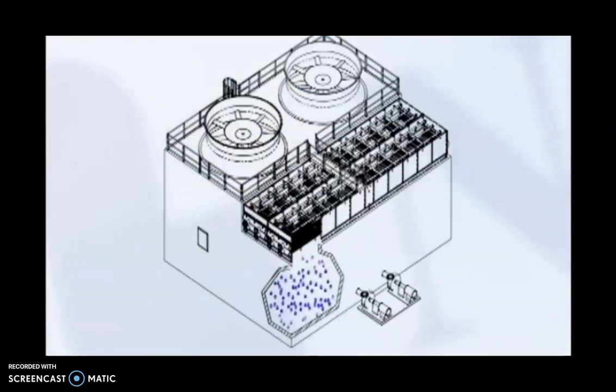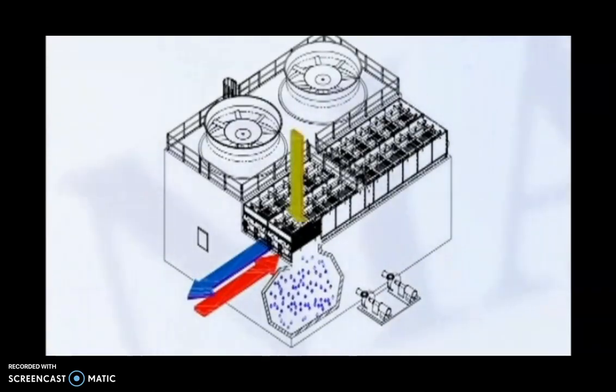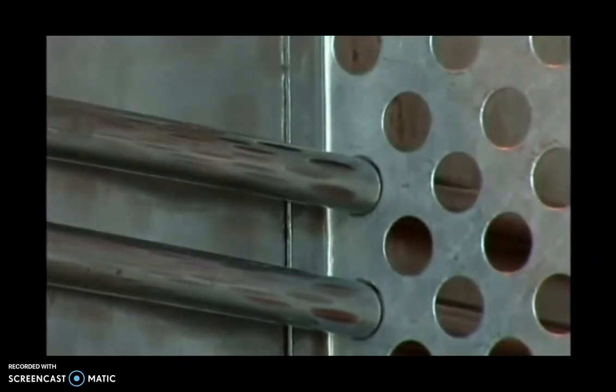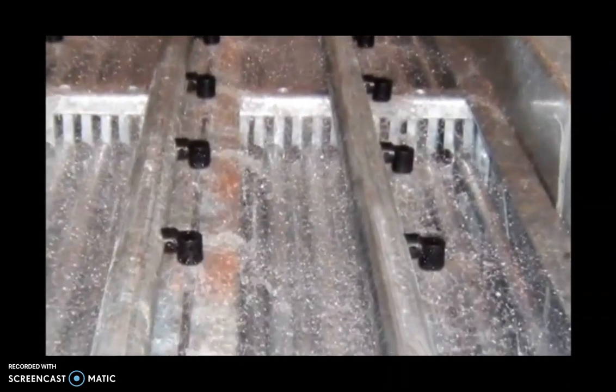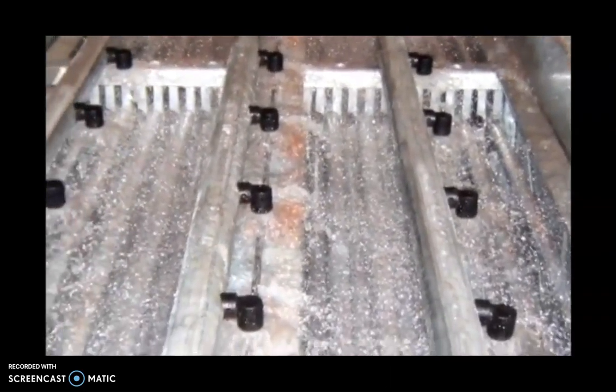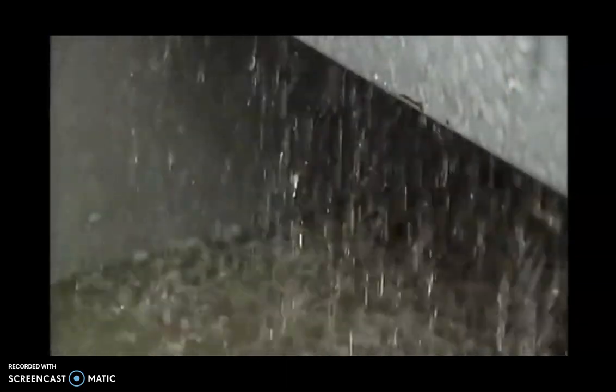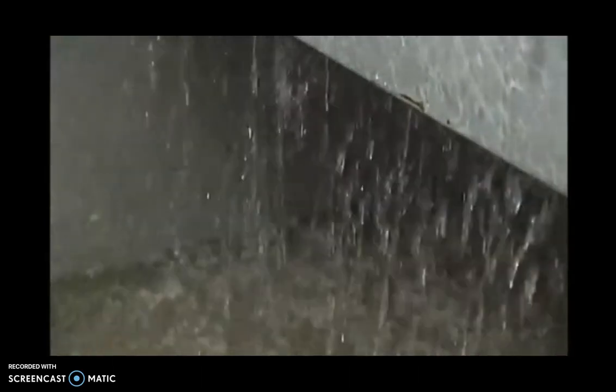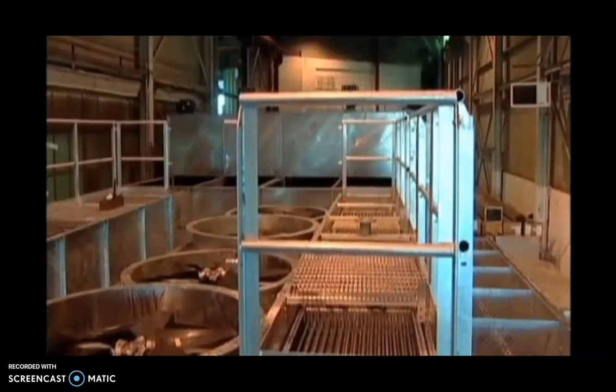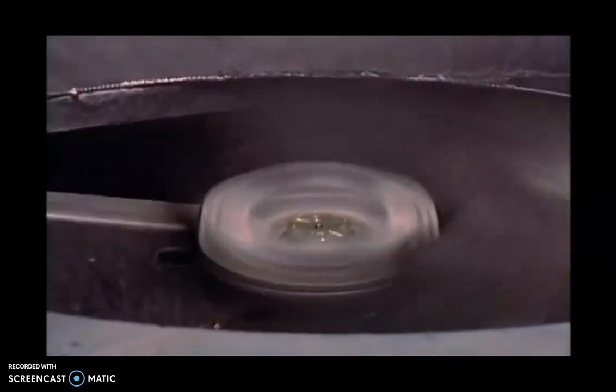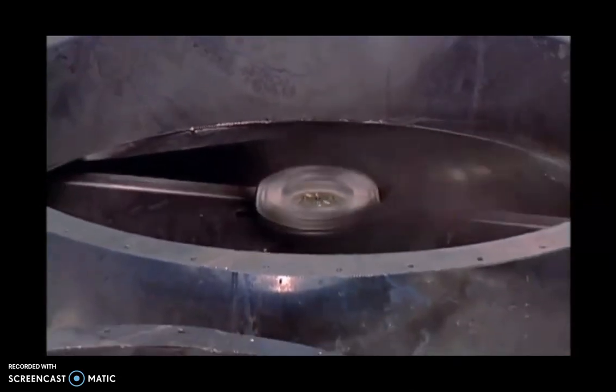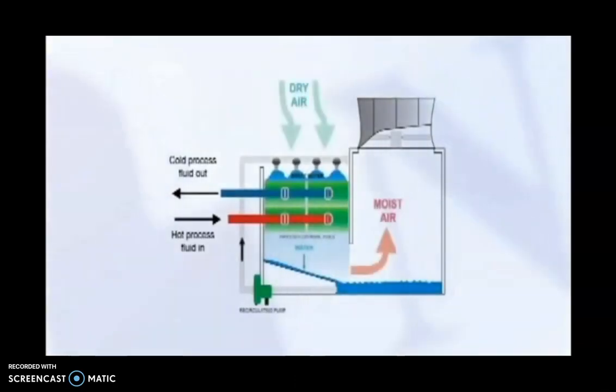Here is a typical wet surface air cooler system. The process stream to be cooled or condensed flows inside specially designed tube bundles. Water is sprayed over the outside of the tubes, and air is induced over the bundles in a co-current direction using fans. The cooling effect takes place at the tube exterior surfaces through latent or evaporative heat transfer. The saturated air and water mixture then makes two 90-degree turns, slows down, releasing any large water droplets back into the basin. The warm saturated air is finally discharged up at high velocity through the fan stacks. Niagara wet surface air coolers are designed with a co-current downward flow of air and water.